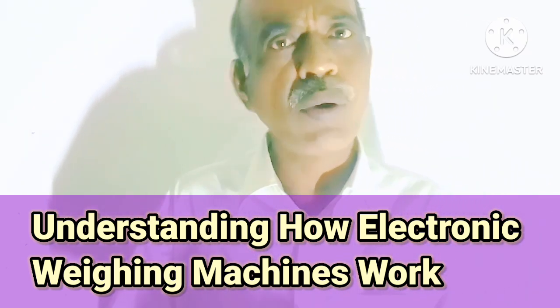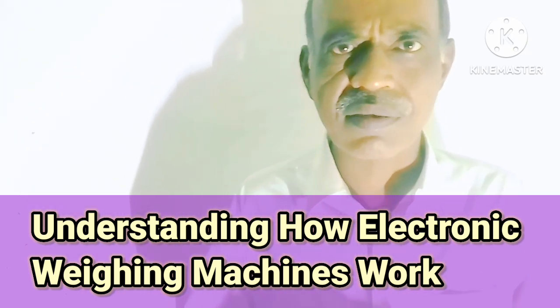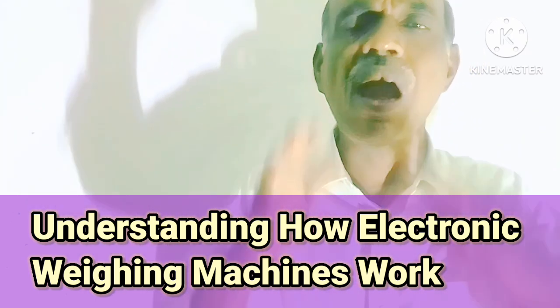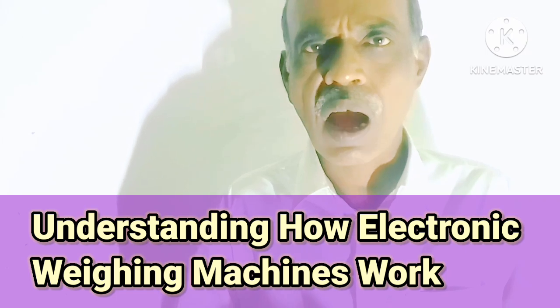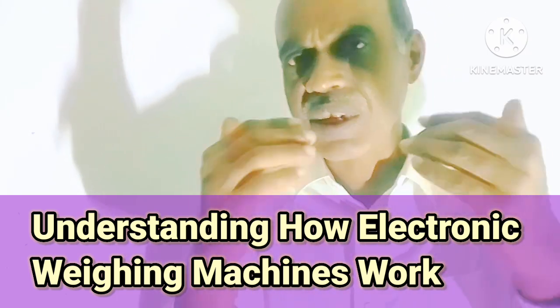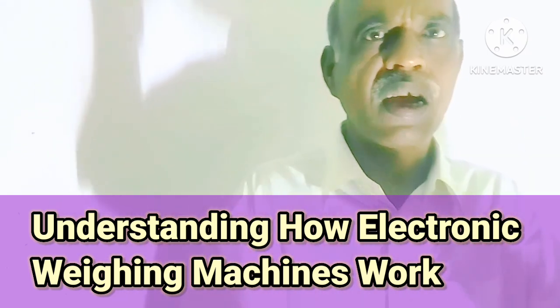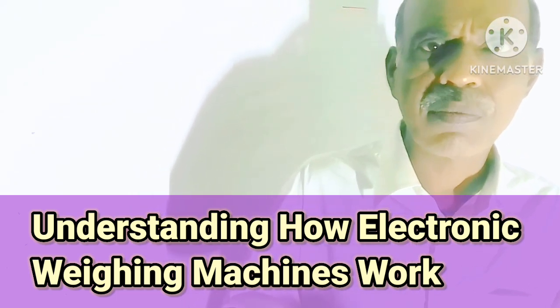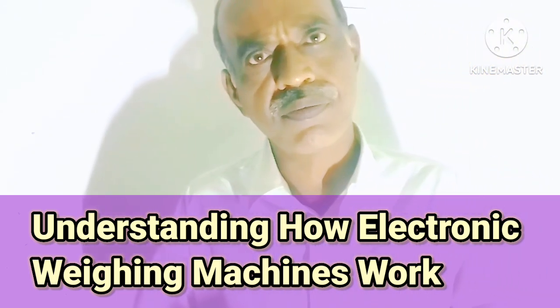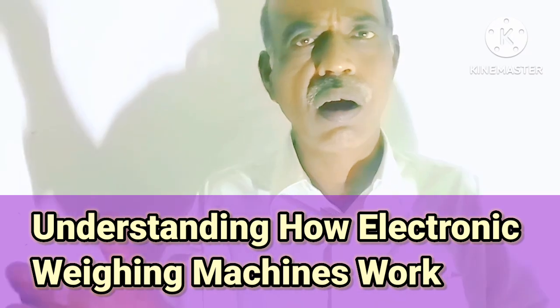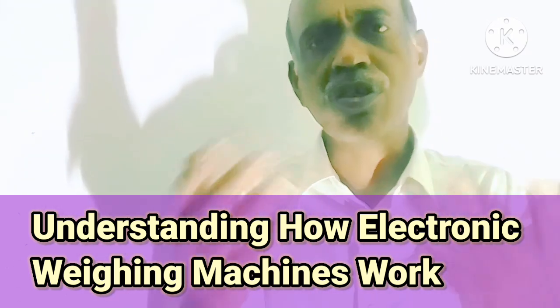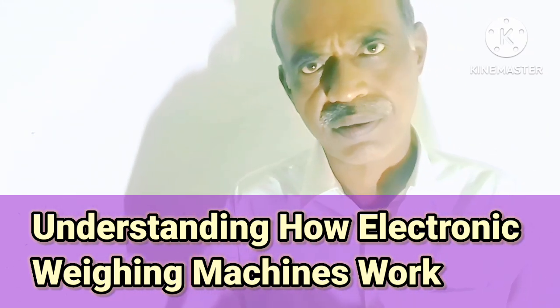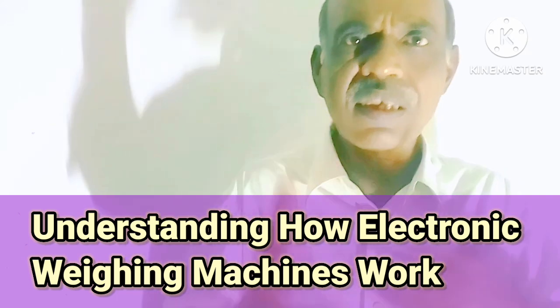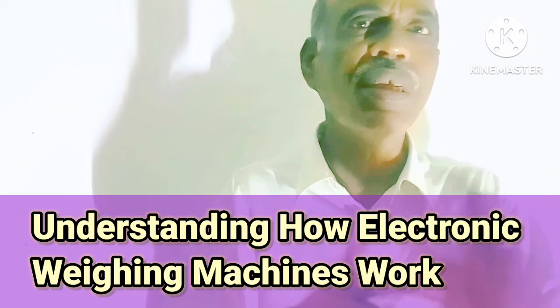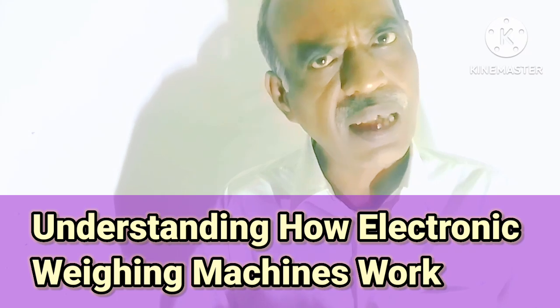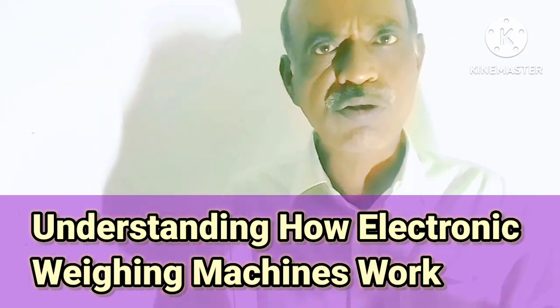The Wheatstone bridge measures the unknown resistance. How does resistance change? Because a strain gauge is being used, there is a change in the length of the strain gauge. Either compression occurs or expansion occurs. In both cases, there is a change in length and accordingly a change in resistance, and that resistance is measured by the Wheatstone bridge.